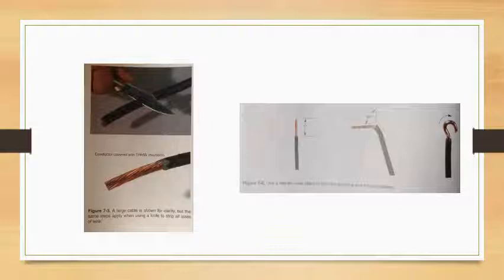Stripping wire. All connections involve stripping some of the insulation from the wire. This exposes the conductor for a good electrical connection. There are many methods for removing the insulation, but the common concern is not to damage either the conductor or the remaining insulation. Using a stripping knife, you can remove the insulation from a single wire by carefully stripping it away with a sharp pocket knife or electrician's knife designed for this purpose. Do this carefully so that the blade does not nick or cut away any of the conductor. Make sloping cuts toward the wire end and away from your body and hands as shown in figure 7-3.